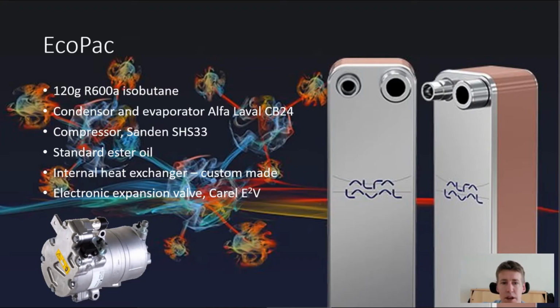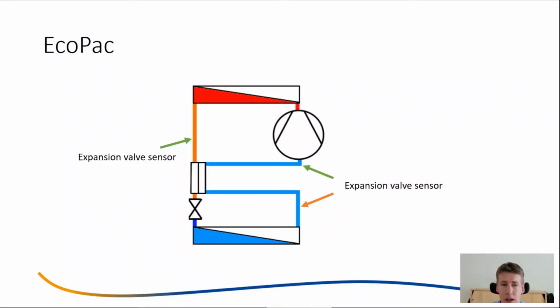The other problem we have with the expansion valve is that today we are measuring the superheat after the evaporator, but after the gas has run through the internal heat exchanger, we get an even higher superheat. And this would be fine if we only have one working point, but since we are running the system in such a different position and such a different revolutions on the compressor, we get really different superheat coming into the compressor, which is not so beneficial for the whole COP of the system. So one idea is to move the expansion valve sensor right before the compressor.